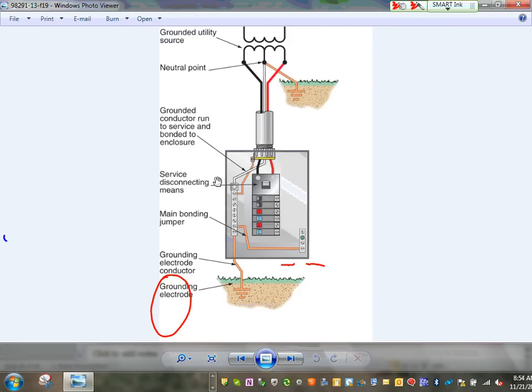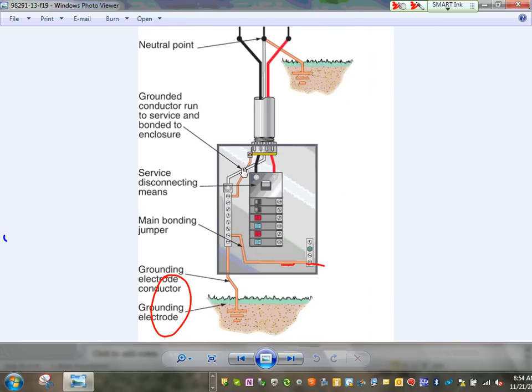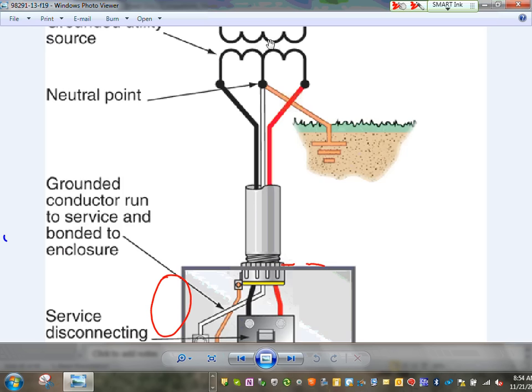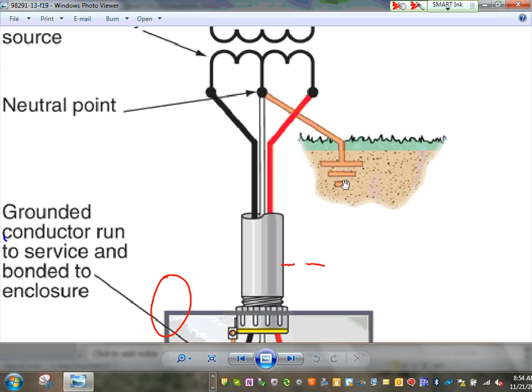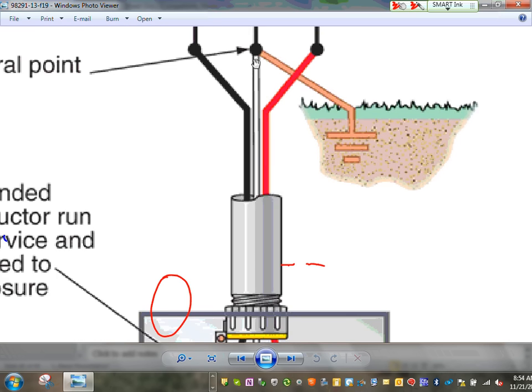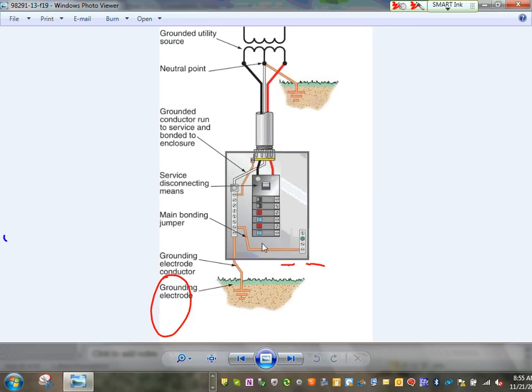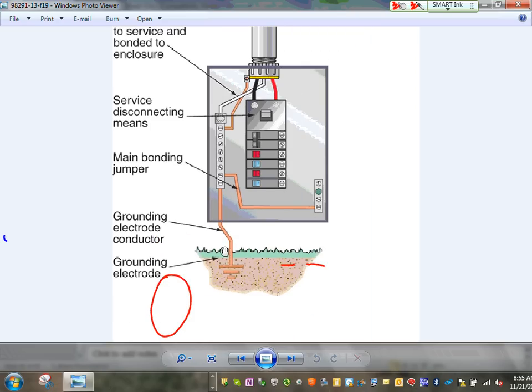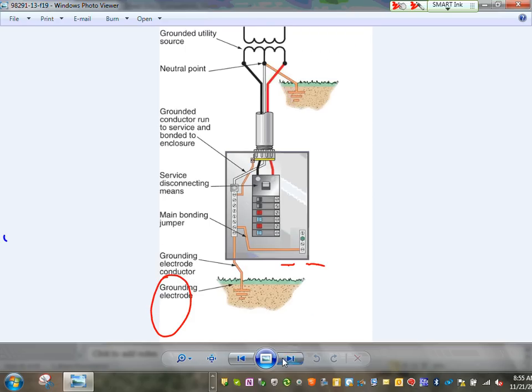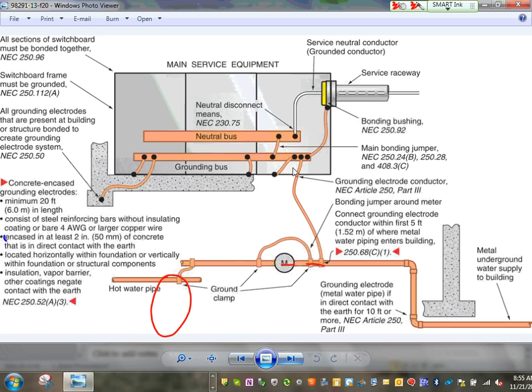Grounding and bonding, guys, very simple. Here's your equipment grounded conductor coming in to the ground bar. You bond it to the enclosure based on the code. And then you take a grounding electrode conductor to the ground rod, which happens to be a water pipe or a ground rod or grounding electrode system. Very, very simple. The utilities, Adam, from their side, they also ground the neutral. Can you see this is done by the utilities here. You in your building, you ground it right in here. You ground it right in here. This is the grounding and bonding, guys.